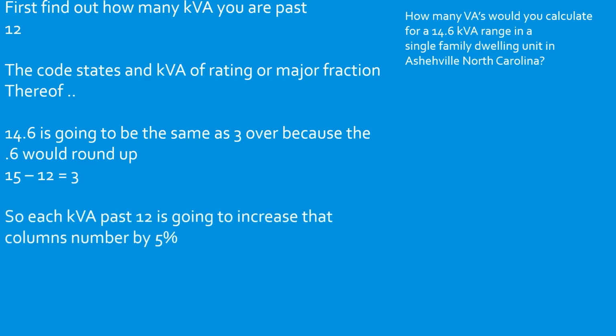Now, it says that for each kVA past 12, we're going to increase the column C value by 5% for each kVA past 12. So we need to figure out our total percentage. It's a multiplier. It's another demand factor. So we take our 3 kVA past 12, multiply it by 0.05. That's going to give us 15%.